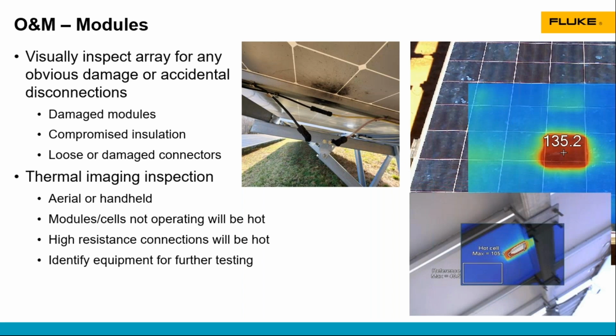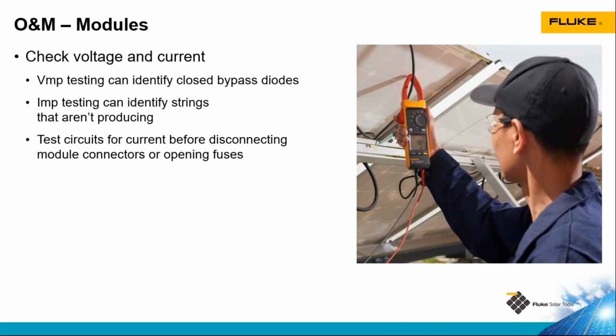We can see hotspots in the modules like we see on the picture here. That hotspot, you probably can't see that just doing a visual inspection, but it's something that a thermal camera will pick up quite easily. We can look on both the front and the back side of the modules like we see here. We can also do voltage and current testing. We can check our maximum power voltage. We can check our operating current levels. Oftentimes in solar, we're doing current tests not to find current, but to see if current is absent.